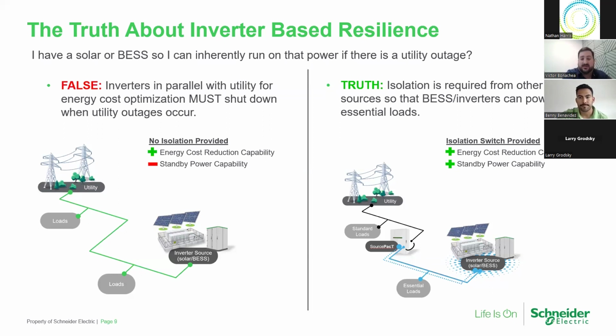However, on the right-hand side, the truth is, yes, you can use it for backup power if you have an inverter that supports grid forming mode, but you just need to also have the proper isolation in your electrical system. Now you see here, we've introduced a disconnect, an isolation point, an interconnect point. You'll hear a lot of those terms used interchangeably. When utility fails, that interconnect point here labeled as SourcePact can open up, basically creating an island, a smaller separate electrical subsystem, a microgrid, if I'm using the buzzword. It breaks off that portion of the electrical system in your facility, and that portion still retains your essential loads that you want to back up, as well as your inverter. Now that inverter is able to come back online and provide power in a grid forming mode to keep those essential loads online.